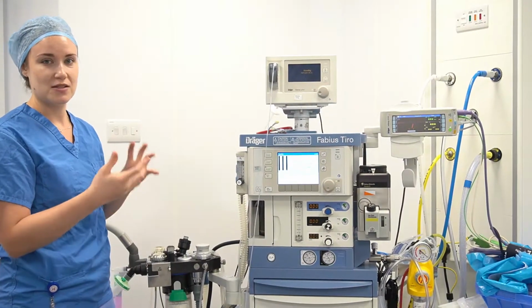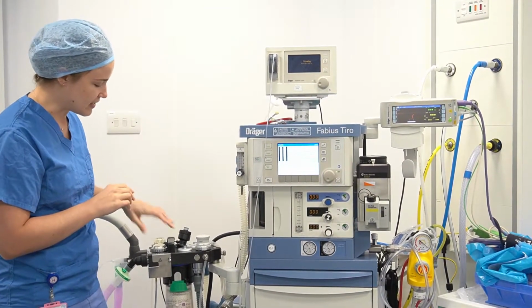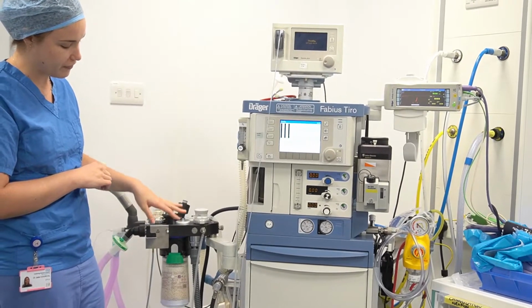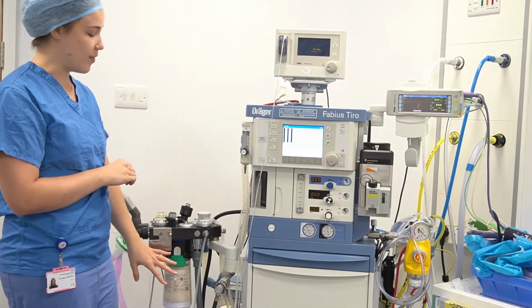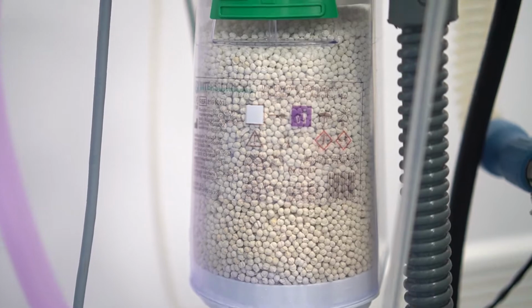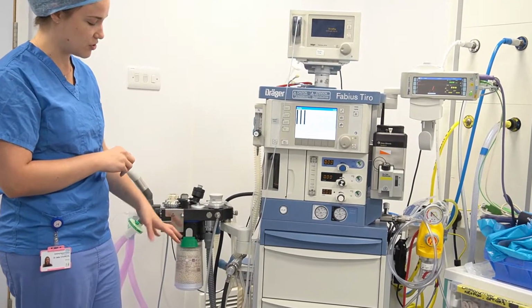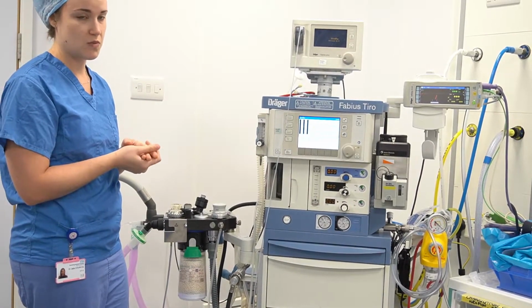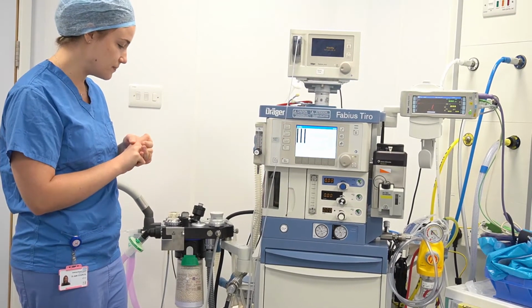While we're doing that, we can just check one or two other things. So basically, just still looking at the breathing system itself. You can check your soda lime, obviously making sure that no colour change has started to happen and that it's basically fresh soda lime, so there's no CO2 retention when you start connecting patients to the ventilator.